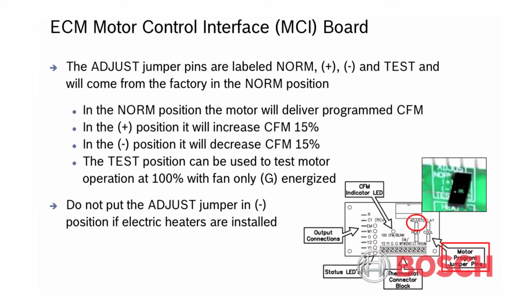The test position allows a service technician to place the jumper in this position, and on a G call or fan only call from the thermostat, operate the ECM motor at 100% to make sure that it is functioning properly.